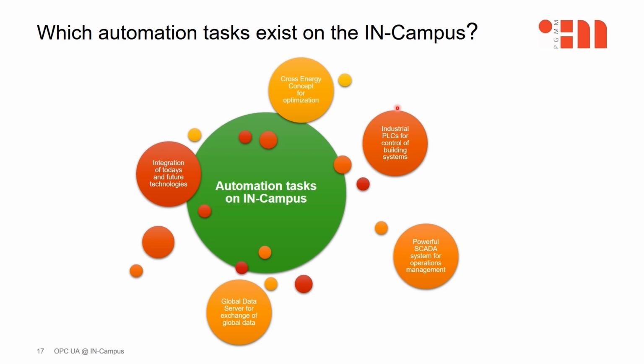The control and regulation of the building systems shall be based on industrial control systems, so-called programmable logic controllers. The operation and alarm management, the reporting as well as the analysis of process data shall be performed on a modern high-performance SCADA system. Local and mobile operating devices shall be able to access individual data points and process graphics of the SCADA system. In order to control the interdependencies of individual controllers, the data exchange between individual controllers is to take place via a so-called global data server.